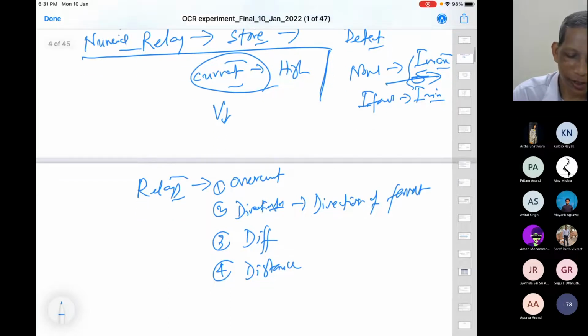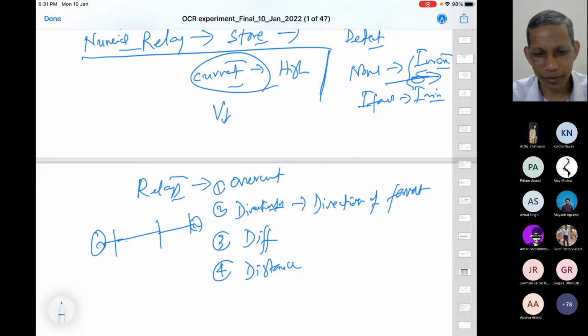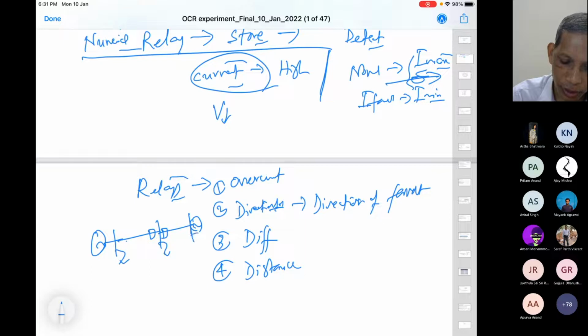Just to quickly go in. Suppose we have a 3-bus system, a very interconnected system, not a radial system like our distribution system. Now, we have a protection arrangement here, a load here, and so on. This rectangular box I am putting is the symbol of a breaker. So, breaker here. For this breaker there will be a relay here, R1. Now, there will be a fault here, which is F1 on the forward side, and a fault can be here at F2 also.